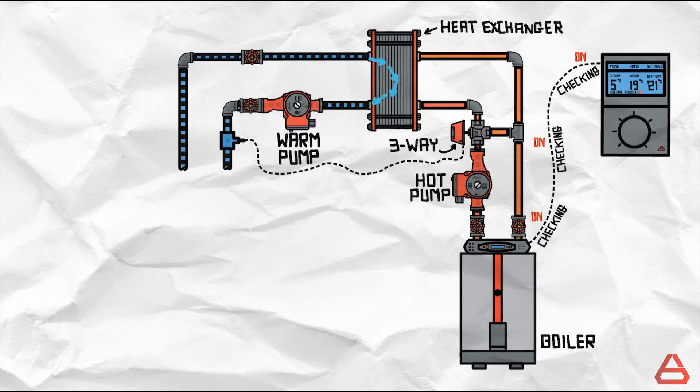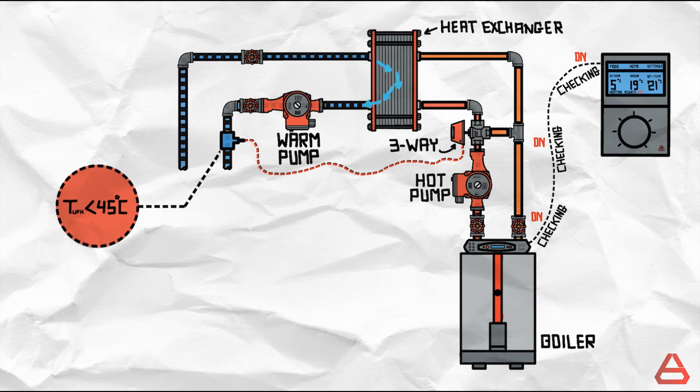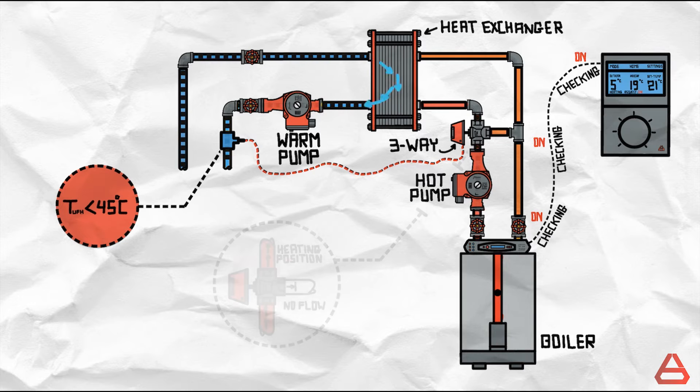The sensor of the three way valve measures the temperature of the water flowing in the warm circuit. It finds that the temperature is below the heating temperature which we had considered to be 45 degrees Celsius. The three way valve will assume a heating position and allow high temperature water from the boiler to enter the heat exchanger and provide heat to the warm circuit.